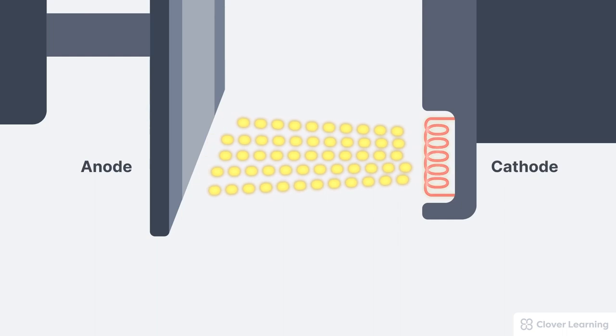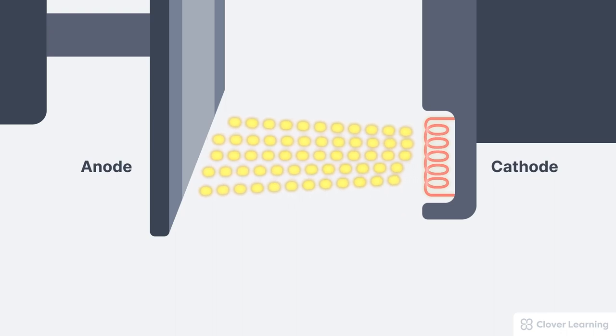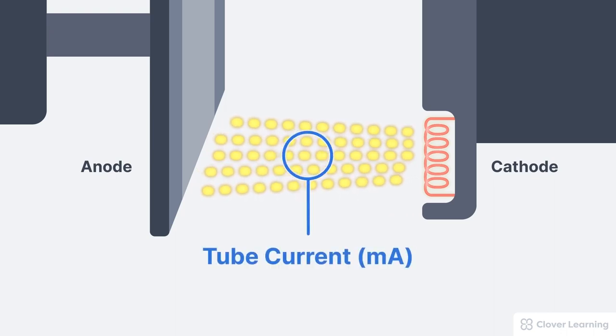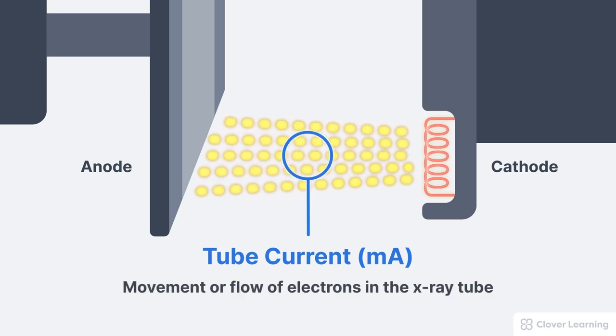X-rays are produced when electrons travel from the cathode filaments and interact with atoms in the anode target. This movement of electrons is what we call the tube current. Tube current is measured in units of milliamperes, which is abbreviated mA. So tube current is simply the movement or flow of electrons in the x-ray tube.